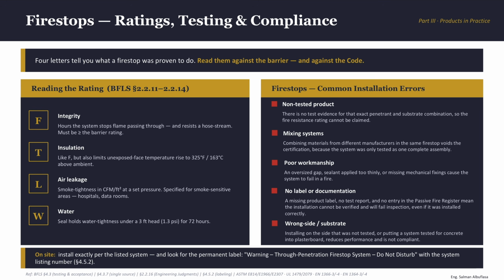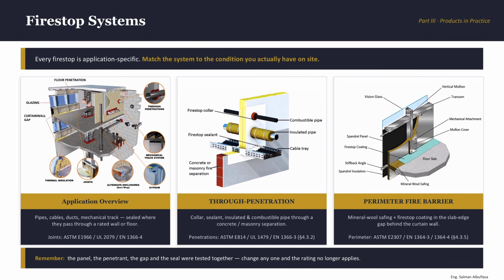So, the discipline is simple. Install it exactly as per the listed system with an experienced contractor, licensed and registered by the local authority. Follow the rules. The first image is an application overview, a cutaway of a building, showing every place a fire stop should live in: floor penetration, mechanical track system, gypsum, alternate enclosures, joints, thermal insulation, curtain wall gap, and glazing. So basically, every one of these orange circle details is a hole that has to be sealed with a tested system, or an opportunity for fire and smoke to pass through.